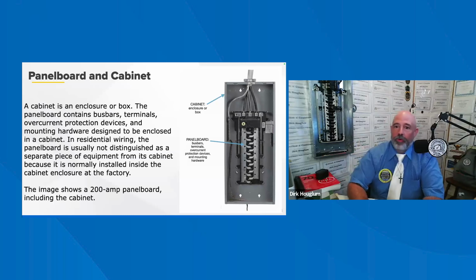Panel boards are rated by how much current in amps they can handle and how many breakers they can hold. By code, every home must have at least 100 amp service, NEC 230.79C. Most modern homes now have about 200 amp panels, which hold about 40 breakers or so. Panels are typically installed as close as possible to where the main comes into the house, and normally on a mounted sheet of plywood. The plywood gives a flat surface for mounting the panel and makes it easy to staple and secure the incoming cables within 12 inches of the box, like it is supposed to.